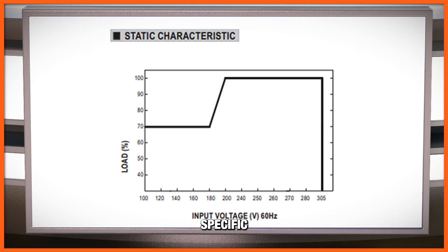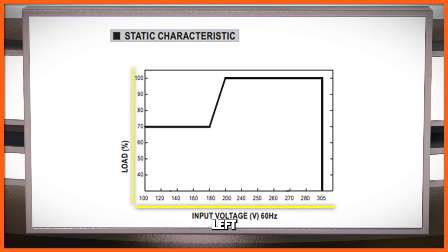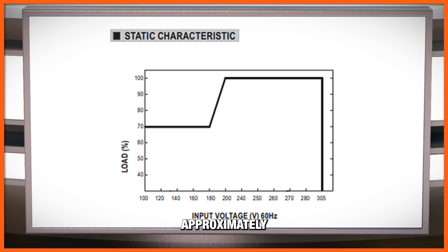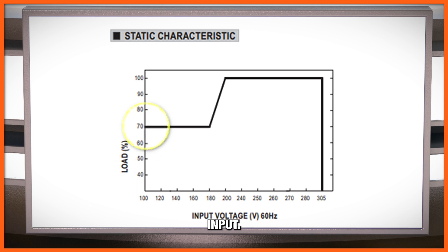In this graph for a specific LED driver, the input voltage you are using is on the x-axis at the bottom and the maximum load percentage is on the y-axis on the left. You can see that when the input voltage to the driver is at 110 or 120 volts AC — this is known as low line — the load percentage shown tells you that you should limit your output to 70% of the maximum output power. That means for approximately 100 watts, your output should not be more than 70 watts using the low line input.